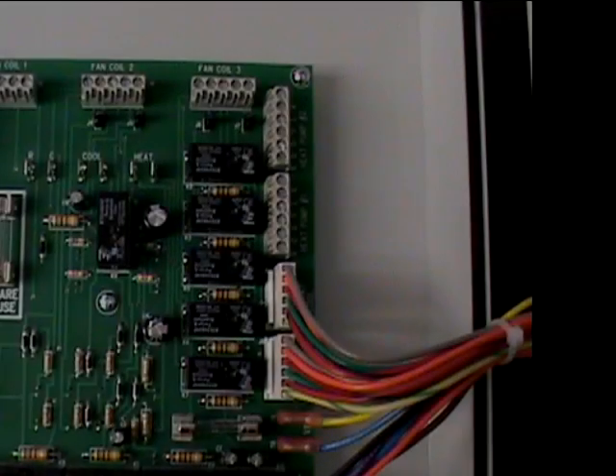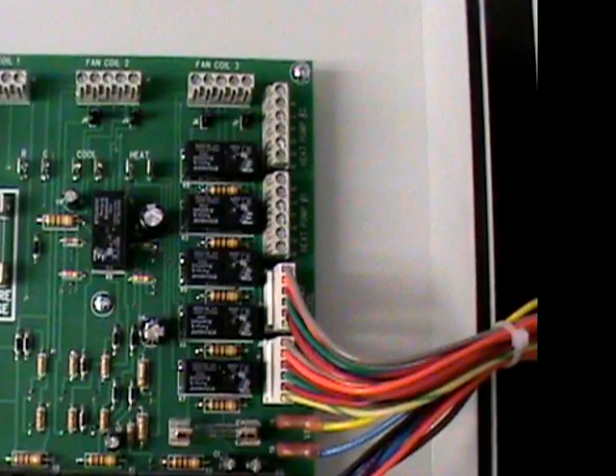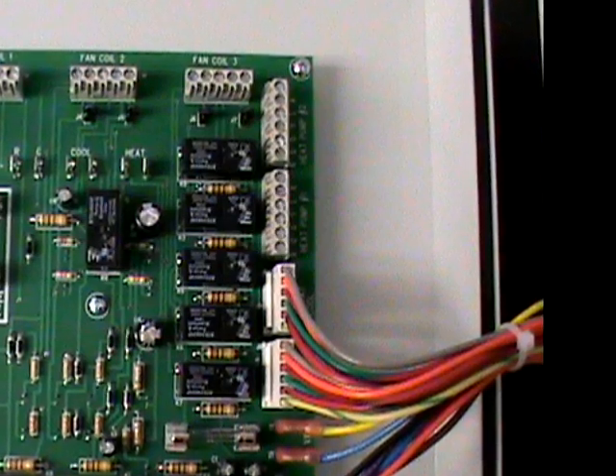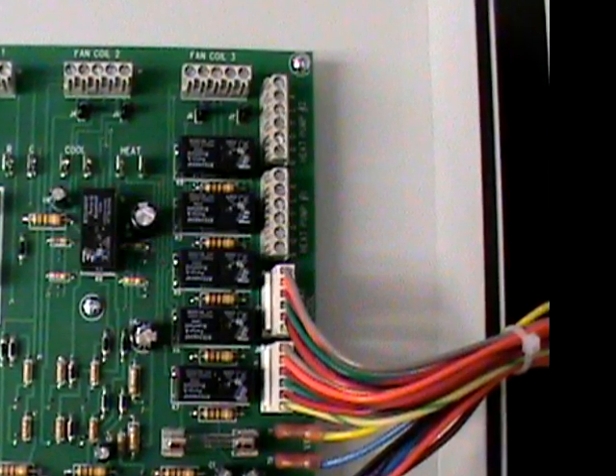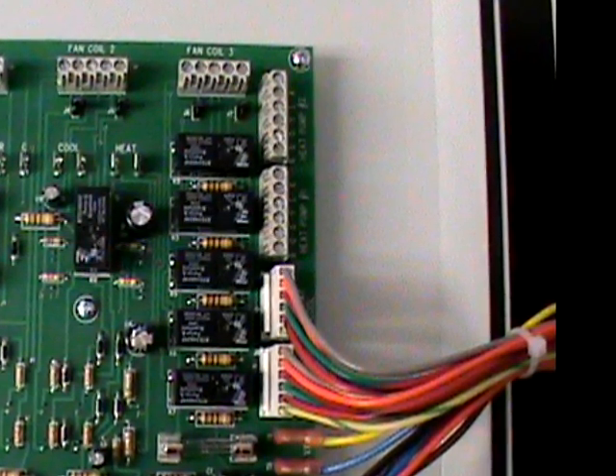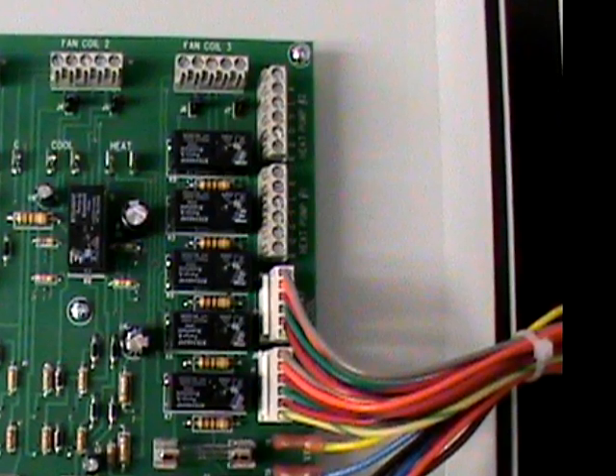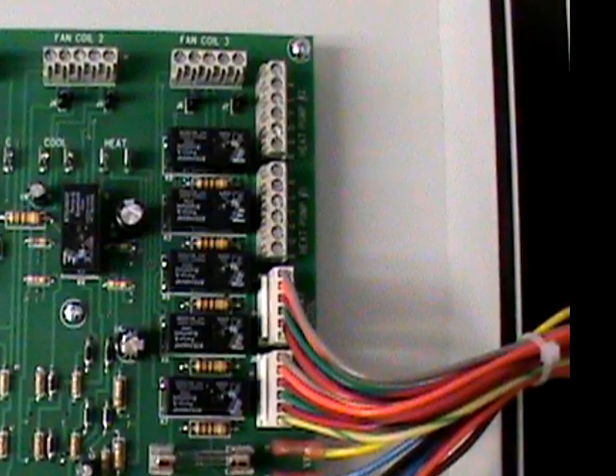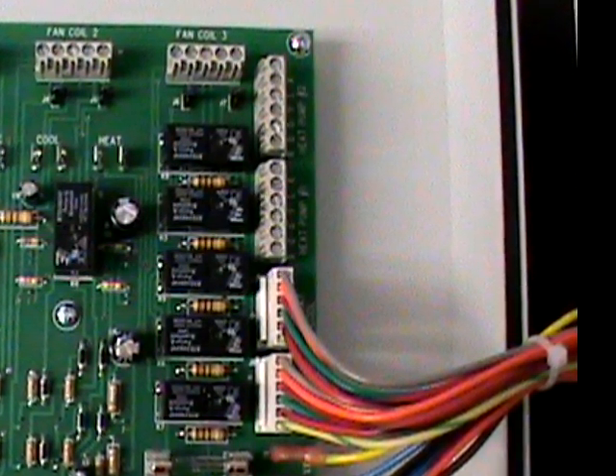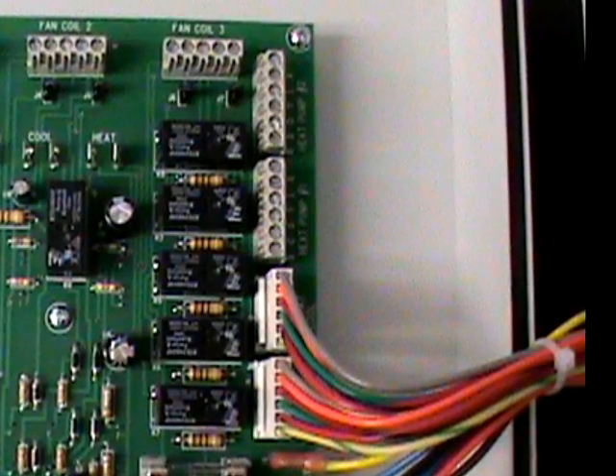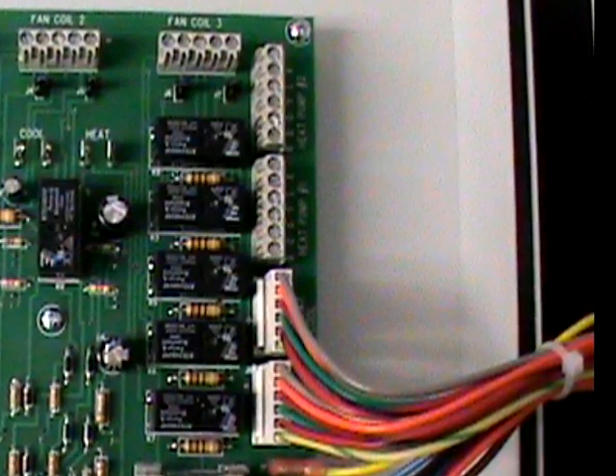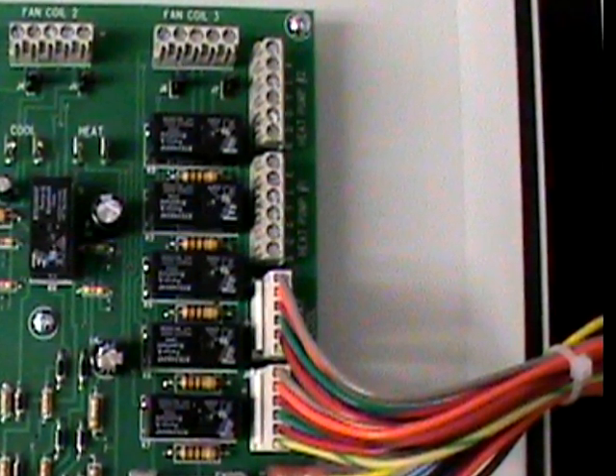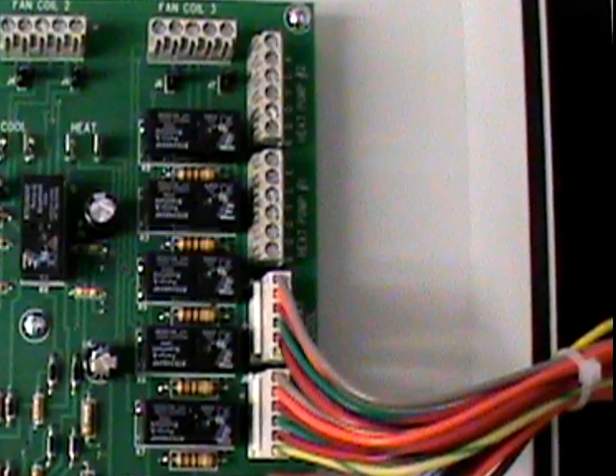As we have mentioned, the control module can control up to 2 hydronic heat pumps or compressors, or a heat pump and a backup boiler. On the upper right side of the circuit board are the terminal blocks for the heat pumps 1 and 2 low voltage controls. Terminals provided include R, G, O, Y, L, and a common terminal X.